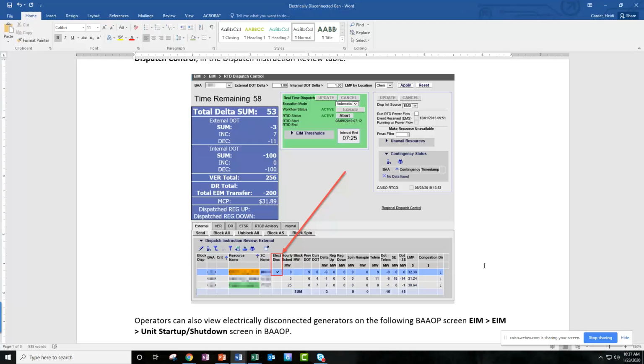So those screens we touched on earlier with the NA output displays, looking at lines and switches, what I'll do is go to that display and look for the same station as the generator that's electrically disconnected, and look at what outages are associated with that substation. Then I'll go into OMS and look at those switches, and then go over to the EMS and say, the SCADA shows these switches as closed, but this outage is modeling them open. In our EMS, we can actually overlay what the market topology is seeing, so we can see that pretty quickly and relay that information back to the EIM operator.